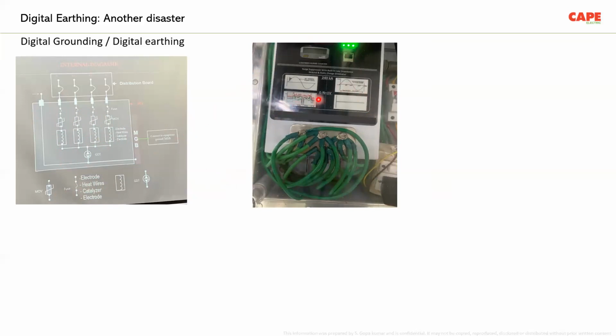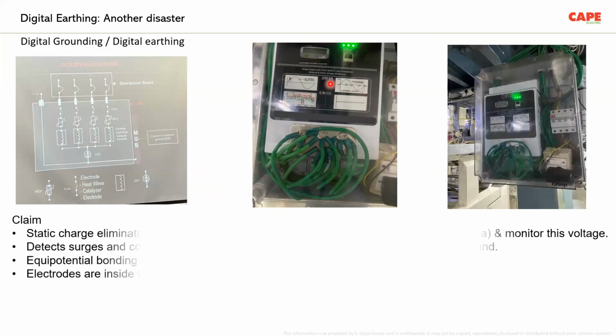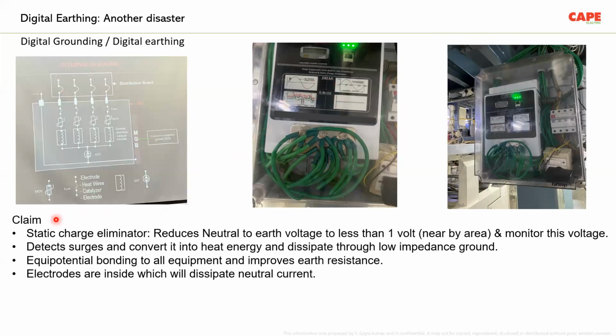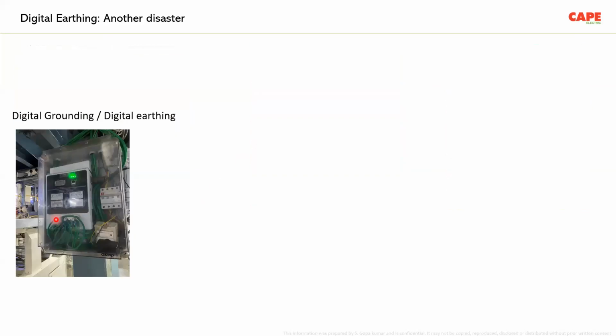They say, you see here, electrode, heat wire, catalyzer, electrode; even they don't know exactly what they are talking about. Basically, this product looks like a black box. So you see here EN, earth to neutral, less than 1 volt. That is their claim, and they also claim a lot of things. The manufacturer claims it's a static charge eliminator. It reduces neutral to earth voltage to less than 1 volt. It detects surges, converts them into heat energy and dissipates them through a low impedance ground. It provides equipotential bonding to all equipment and improves earth resistance. Electrodes inside will dissipate neutral current. Actually, this product comes with a beautiful catalog which contains a lot of claims.